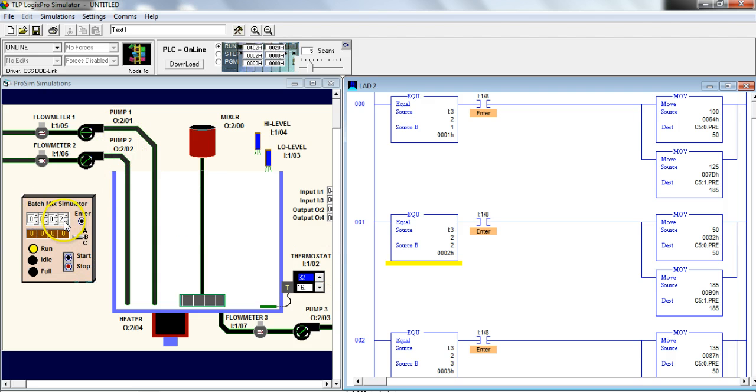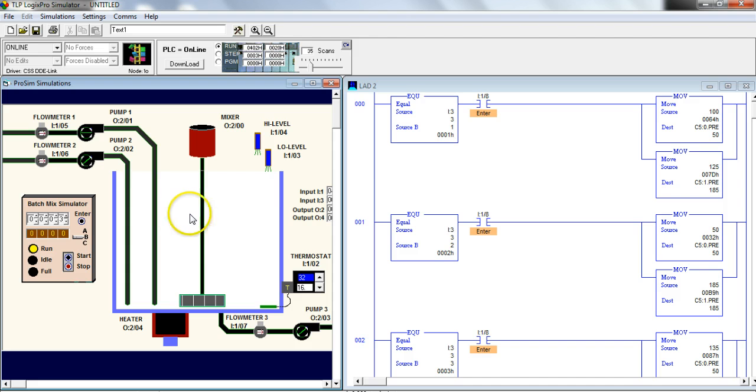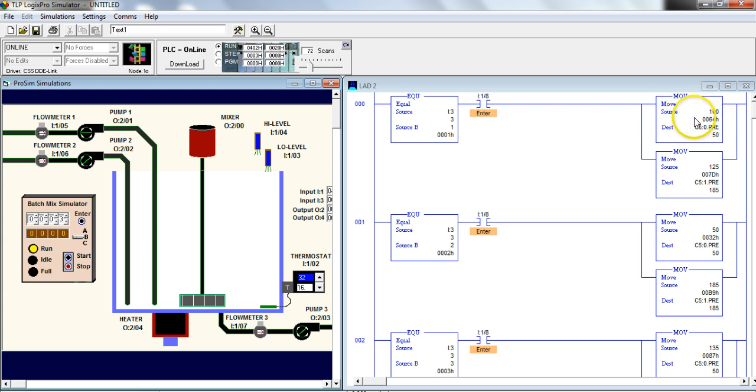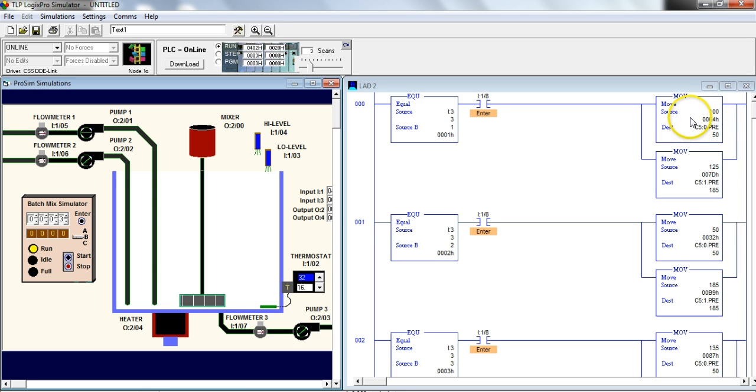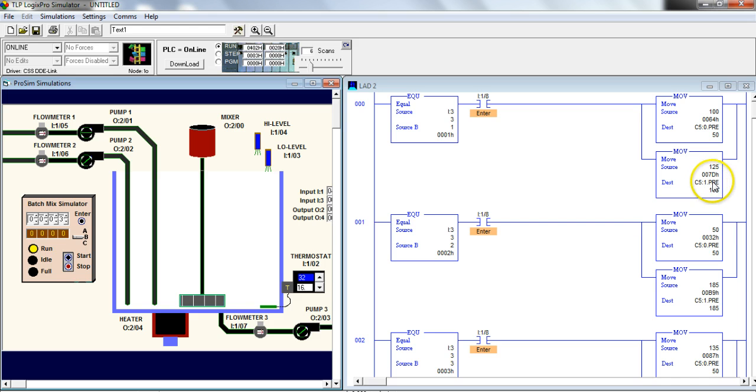So here's my little recipe selector here. If I select recipe 1, I'll pump different amounts of product. Recipe 2 will be a different amount of product and 3, again, different amounts. And the way that's done with the MOVE instruction is, if you look at this MOVE instruction here, it's going to move a value from one source to a destination. So in this case, I'm moving a 100 into this counter 5-0 preset. And right below it, I'm also going to move 125 into counter 5-1 preset.